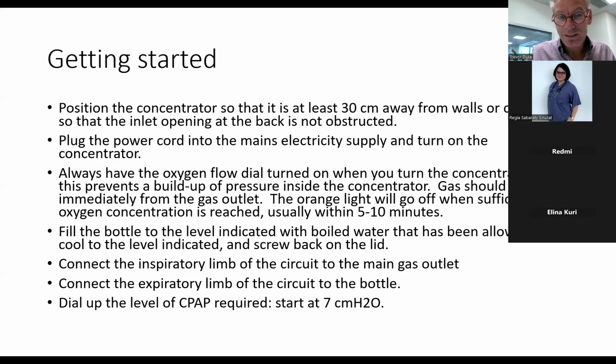Obviously, plug the power cord in, turn on the concentrator. Whenever you turn on an oxygen concentrator, always have the oxygen or the gas flow dialed up. You have to have it turned on. If you don't have that, then the machine ends up generating gas flow, and there's nowhere for it to go, because the flow meters are turned off. If the flow meters are turned off, then there's a buildup of pressure inside the machine. So all you have to do is turn the oxygen and the airflow on before you actually turn the power on. That's all. Then gas will flow immediately from the gas outlet.